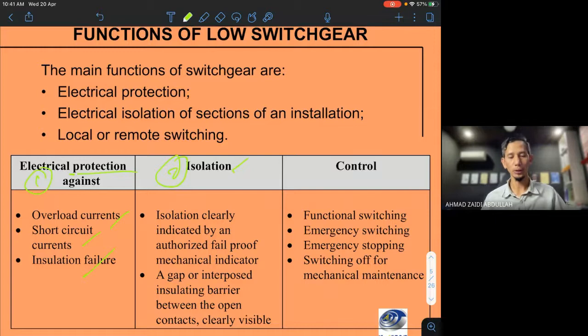And then number two is isolation. So the isolation is by a fail-proof mechanical indicator or a gap or interposed insulating barrier between the open contacts clearly visible. Ini kita nak asingkan, memang to isolate. Okay, the switching switchgear. Okay, and then number three is control. We want to control it, to make it functional switching, emergency switching, emergency stopping, and then switching off for mechanical maintenance lah.